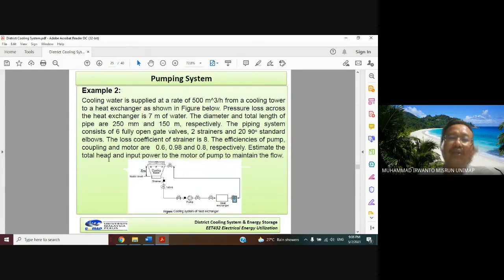Now we want to find the total pressure losses. We need to calculate friction losses for the pipe, friction losses for the fittings - for fittings alone there are 6 gate valves, 2 strainers, 20 90-degree standard elbows.